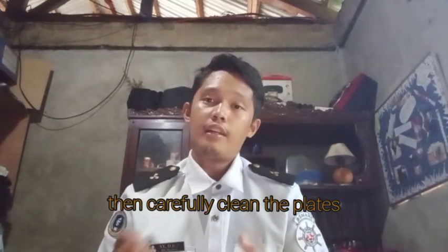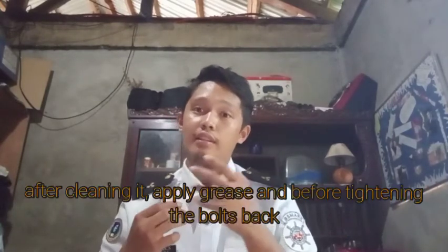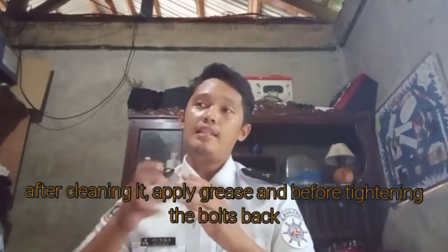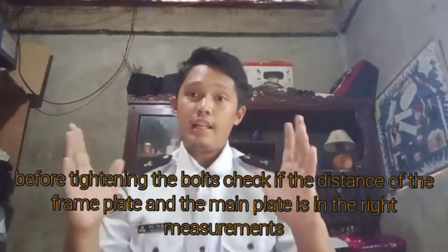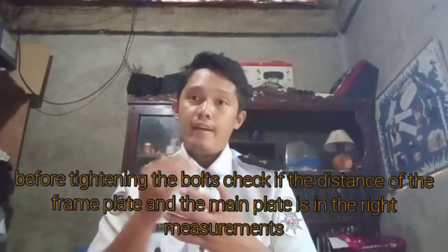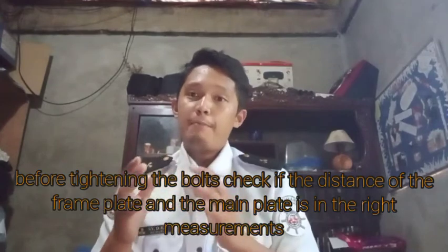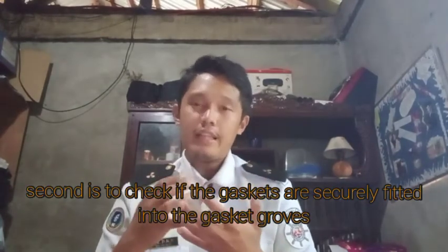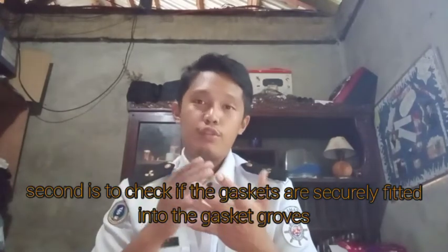After cleaning, you should check if there are damages. You should always apply grease on the tightening bolts and the locking bolts so that you can easily turn them into their places. Before tightening the tightening bolts, you should first check if the distance between the frame plate and the main plate is exact by measuring it with a push-pull rule. Also, before tightening the bolts and the locking bolts, check that the gaskets are securely fitted inside the grooves of the gasket.